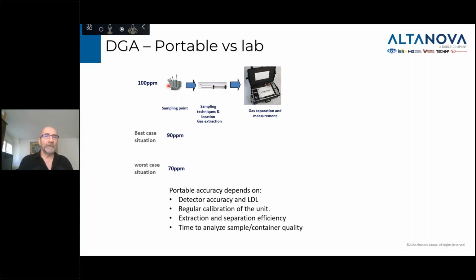So again, if you start with 100 ppm and that whole system is under control, you have a high probability of getting a measurement of around 90 ppm. So the whole system has an accuracy of plus or minus 10%, which is pretty good in general. The worst case we've seen is results of 70 ppm. Why 70 ppm? Because portable accuracy depends on a couple of factors. The first is the detector accuracy. What kind of technology are you using? Each detector has a specific accuracy range, and also a lowest detection limit. Every detector, whatever the technology, has a different LDL.